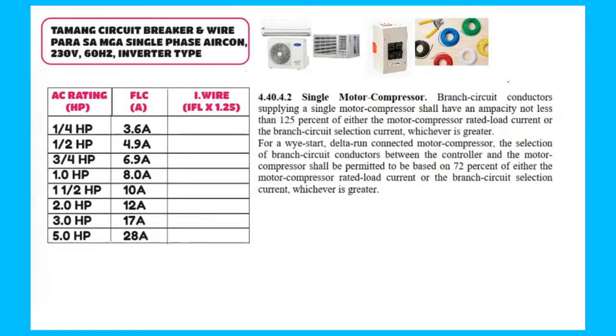From the data kanina, so ito ngayon yung magiging computation natin to size up the wire ng ating aircon unit. So from the table, meron tayong full load current expressed in amperes. So sa table ito kanina nagamit natin, merong sinabi sa PEC 4.40.4.2 for single motor compressors, that ang branch circuit conductors or ito yung wire supplying a single motor compressor shall have an ampacity not less than 125% of either the motor compressor rated load current or branch circuit selection current, whichever is greater. So to size up ng magiging wire ng single motor compressor, so dapat naka-mark up siya na 125%.